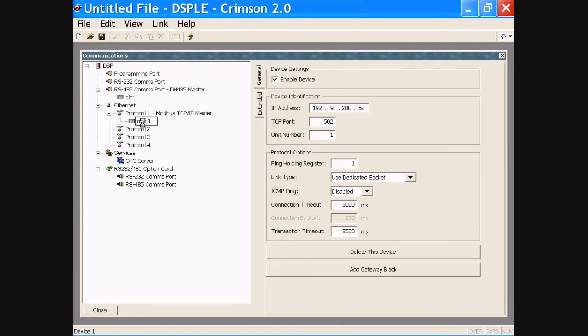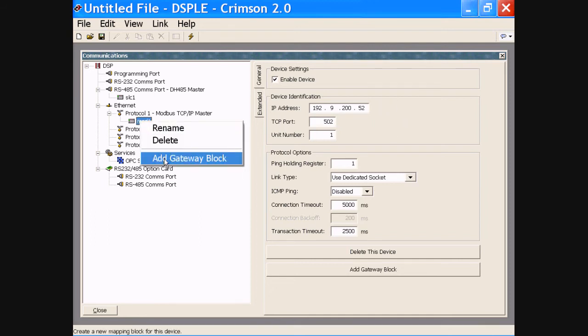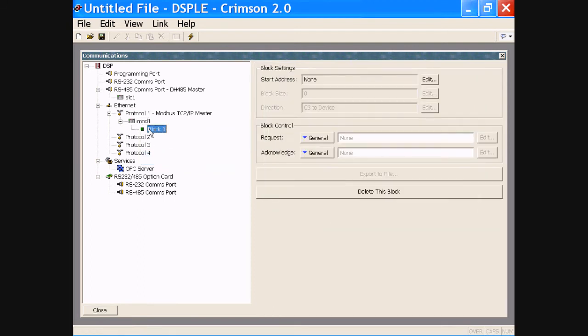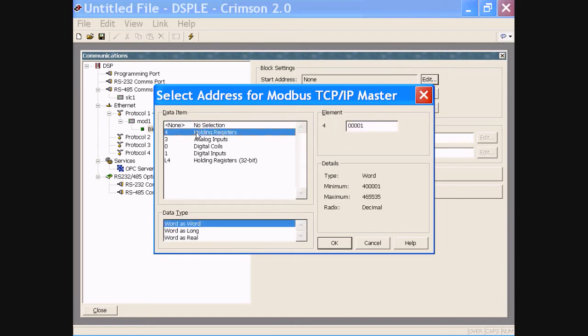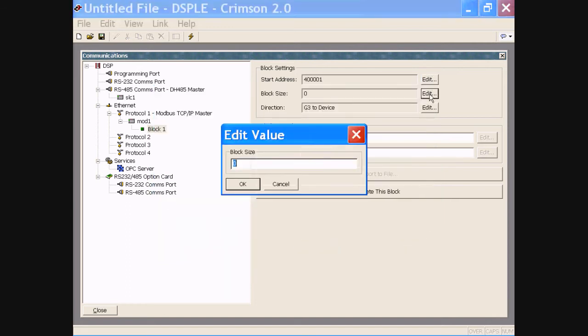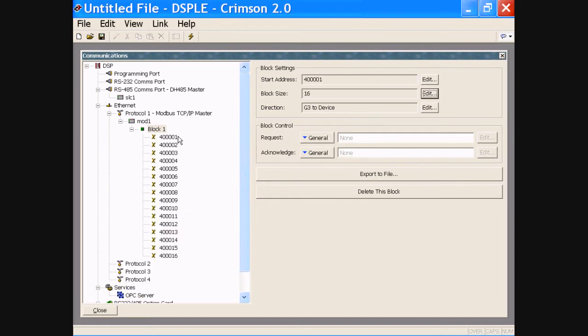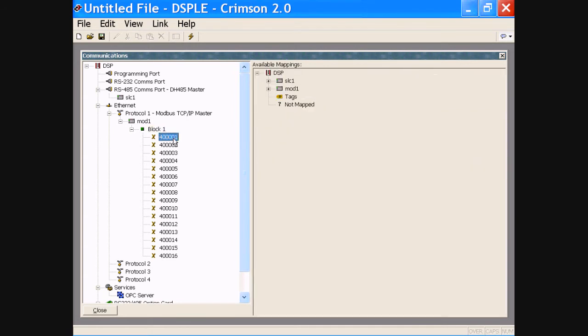Here we pick an IP address for this unit. Now that we have a couple of devices, we can add what's called a gateway block. In the gateway block, we're going to pick registers internal to the PLC — let's say the 40,000 registers for the Modicon. How many do we want? Let's say 16. So now I've got 16 40,000 registers, and if I pick one of those registers it shows me the available mappings.